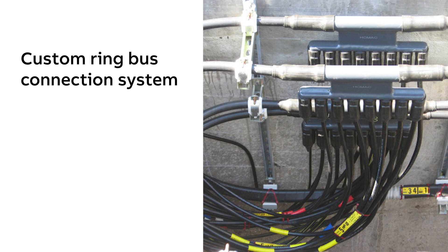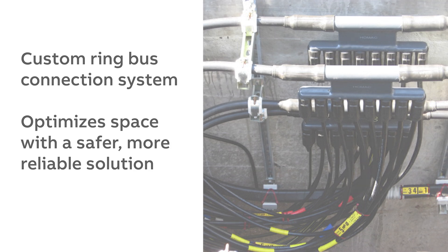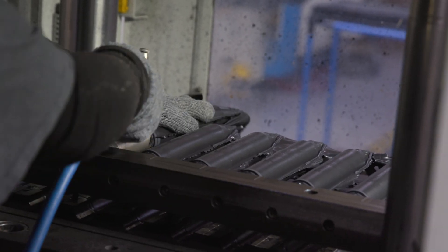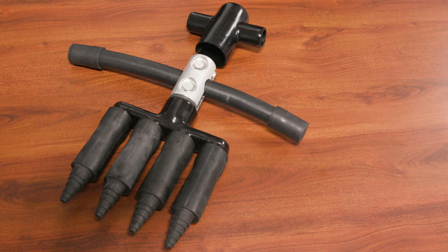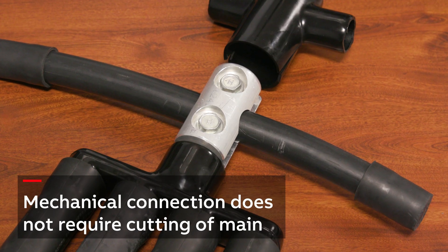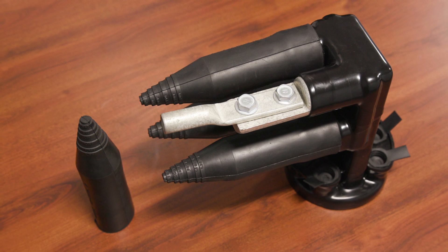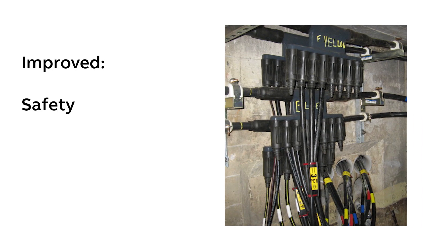In the end, the customer decided to renovate the whole vault using a ring bus system we designed for them, including a HOMAC flood seal ring bus connector. HOMAC flood seal connectors are insulated with PVC and EPDM rubber to ensure watertight connections. The ring bus connector uses compression or set screw technology to tap from the main bus and allow connection up to eight services with mechanical set screw connectors or compression lugs.